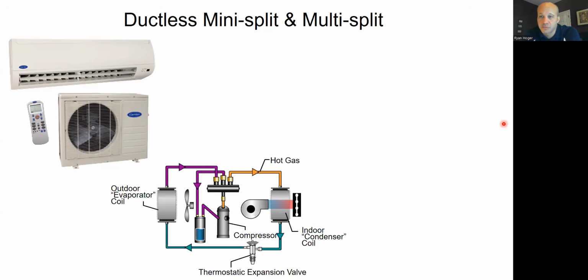So you'd buy this ductless mini split. You throw it in there. It would be one that had low ambient cooling because you could run cooling when it's 0 degrees out, and that would be it. That's what you're going to find mostly in the existing market in commercial buildings. And there's no reason to swap that to a heat pump because that application doesn't need heat. However, when you get a new ductless mini split, it's going to be a heat pump because almost no one makes cooling only versions of these anymore. There are a few, but generally 90+% of the market is heat pump version. So the AC one dies, you put the heat pump one in. You just don't ever put it in heat mode because you don't need heat in that server room. So we're not talking about those applications because those ones obviously don't need any heat.